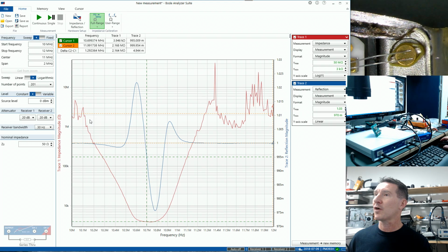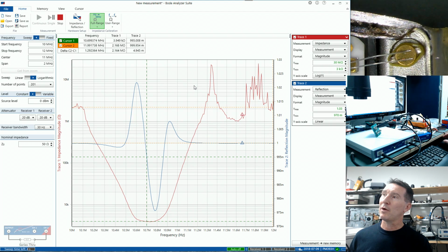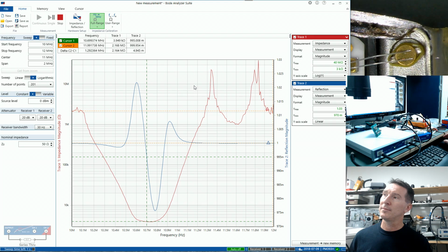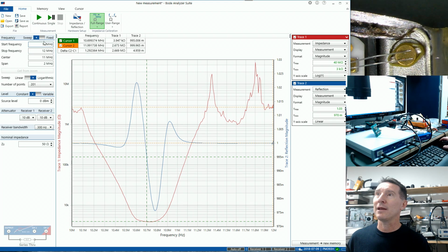Let's drop that by an order of magnitude down to 30 Hertz, and let's sweep that again. And yep, we're getting an improvement. It's going to be slower, of course, with the lower receiver bandwidth, but we should see this clean up a tad. Bit more accurate. Yep. Go back to 300. Drop that down to 10 dB. Run it again. Yeah, it's a bit better. There you go.